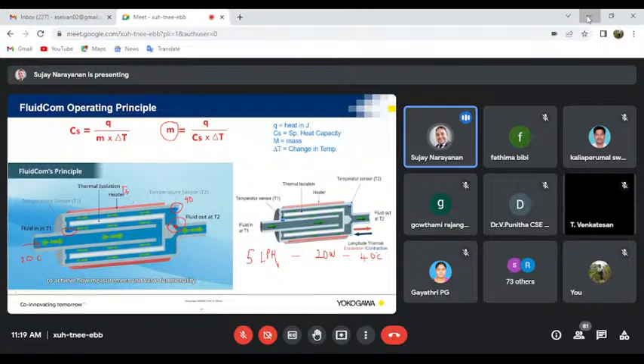due to a non-expected operation or a hazardous operation will be contained within the instrument, because it is designed to withstand a certain temperature of explosion without compromising the surface temperature of the instrument when an explosion occurs. Okay, thank you, sir.